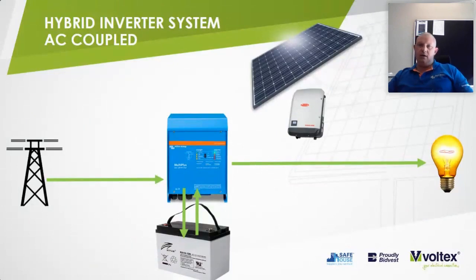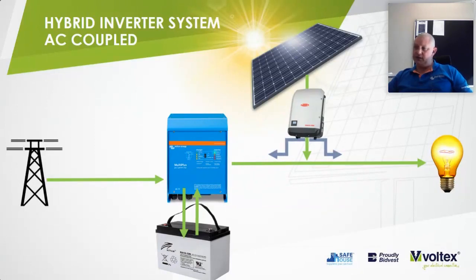This adds a grid tie inverter to the equation. So the grid tie is connected to the output of your battery inverter. Thus, the inverter generates a 50 hertz frequency, giving the system the frequency to power up and feed power to your loads, and in turn, feed power back to the inverter. And as I mentioned earlier, this is a bidirectional inverter. So the excess power fed back that is not being utilized by the loads can be fed back into the inverter and the batteries can be charged from this source.